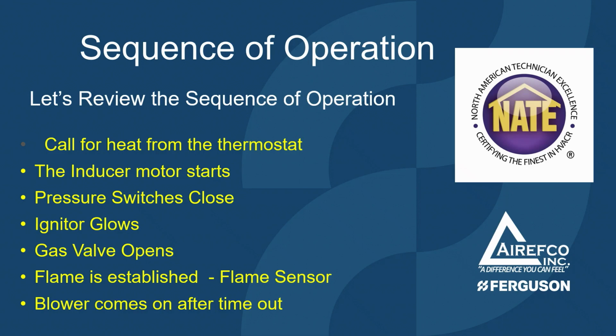First, there's a call for heat from the thermostat. Then the inducer motor starts, and the pressure switches close. The igniter glows, the gas valve opens up, and the flame is established by the flame sensor. And once the timer times out, the circulating blower comes on. It's very important for a technician to know the sequence of operation of a system so that you know what it should be doing versus what it is doing.